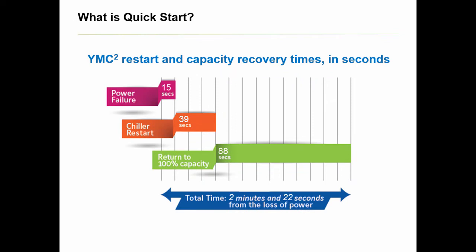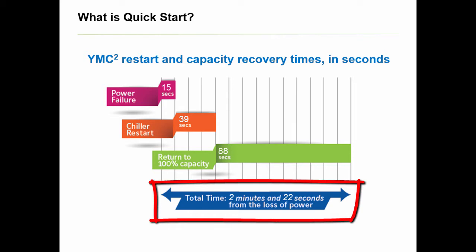And depending on the application and operating conditions, we've seen YMC-squared chillers get back to full capacity in less than two and a half minutes following a power loss, which far exceeds typical industry centrifugal chiller times.